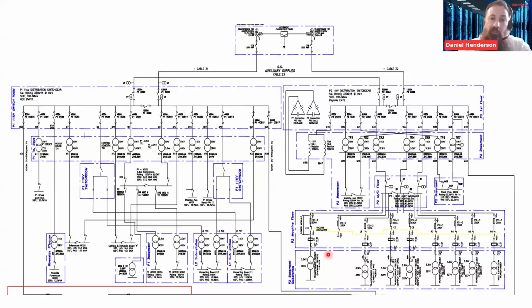So what I've done is, there's no indication of anything that could be a risk to me. Nobody's seen anything that could have potentially caused the fault. So I've gone to this nearest substation, which is a 66 kV to 11 kV substation, and I've identified that this circuit breaker is tripped. However, everything else in that substation, there's no signs of a breach of integrity. There's no leaks. There's no signs of overheating or damage that I can visually see. So that's tripped on overcurrent on that electromechanical relay.